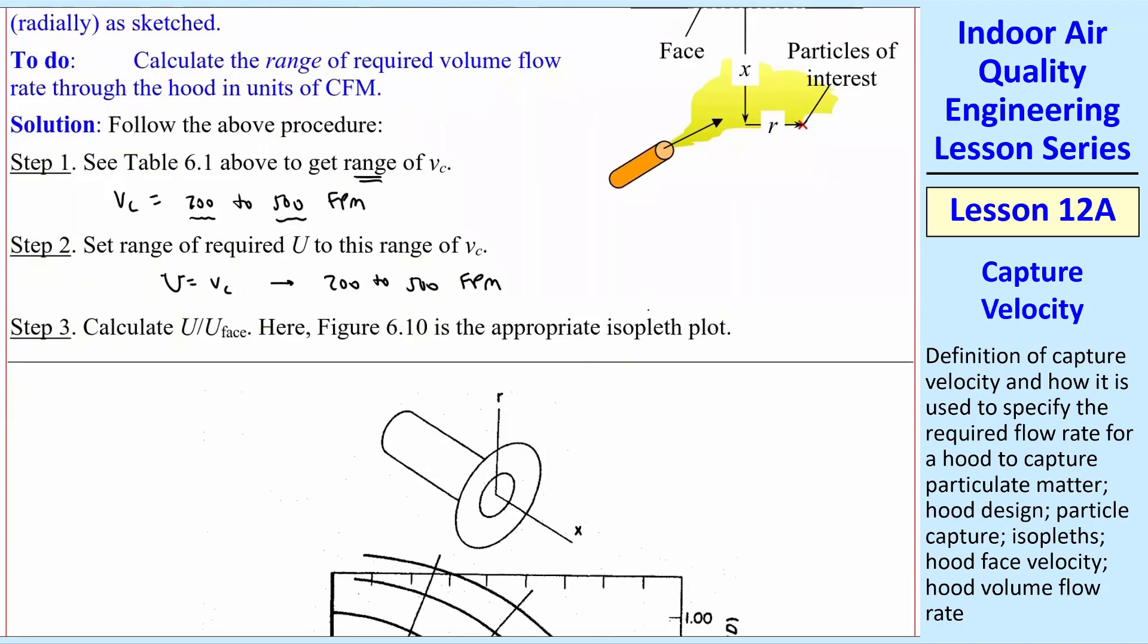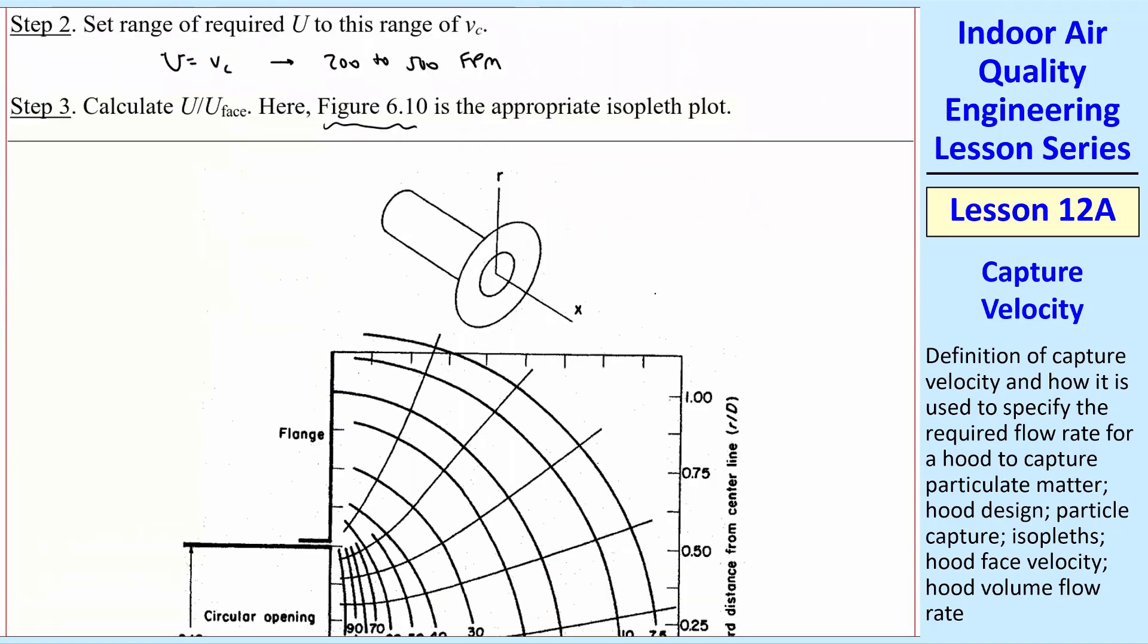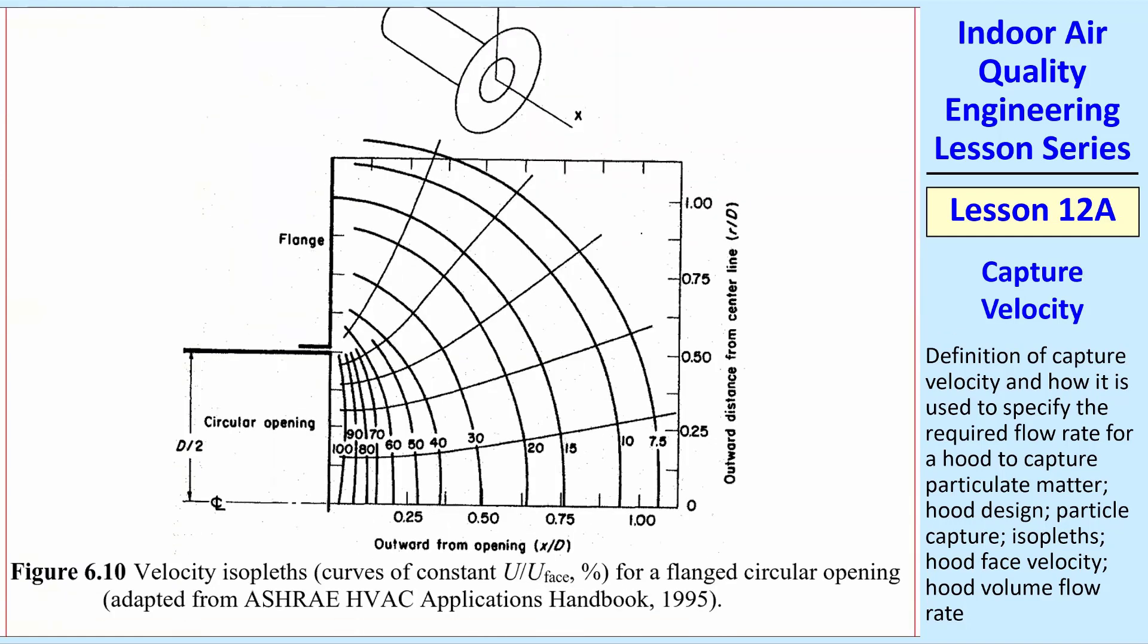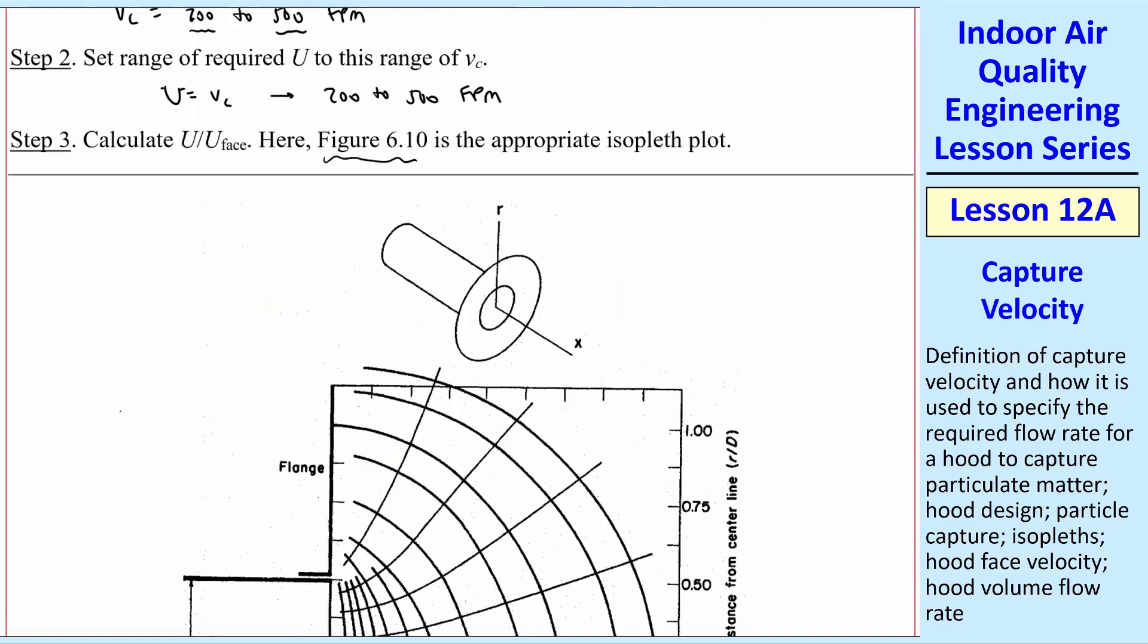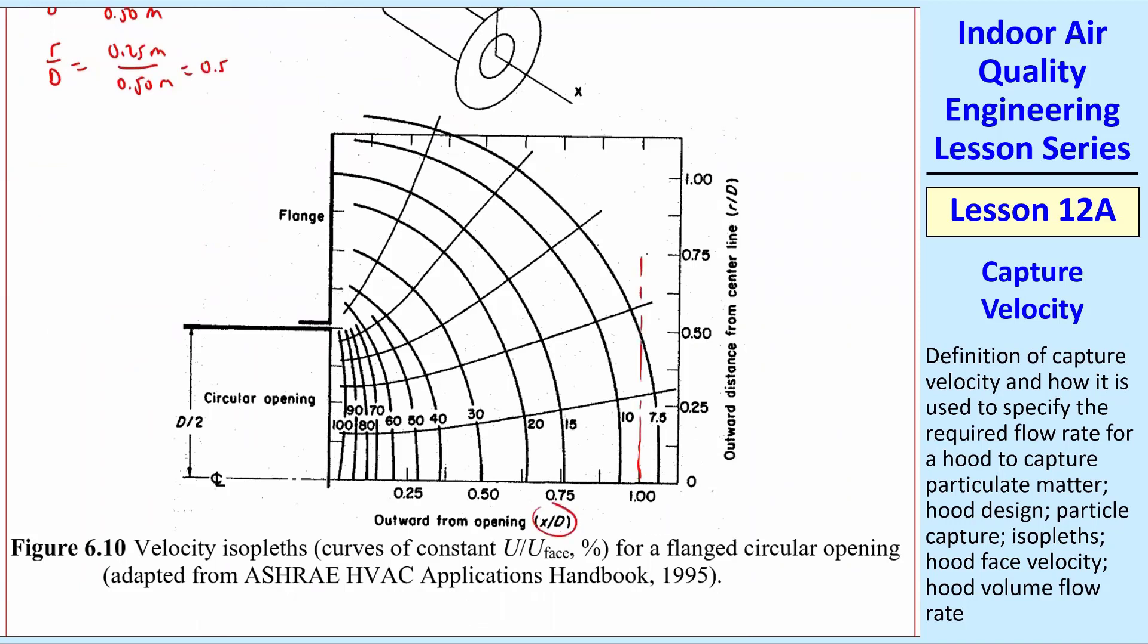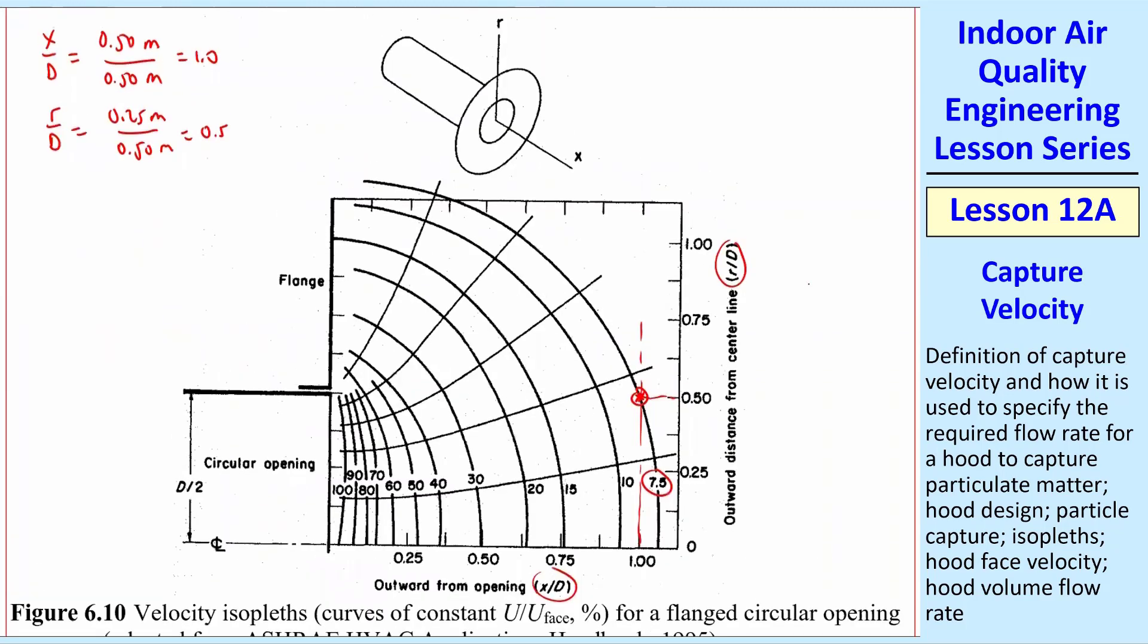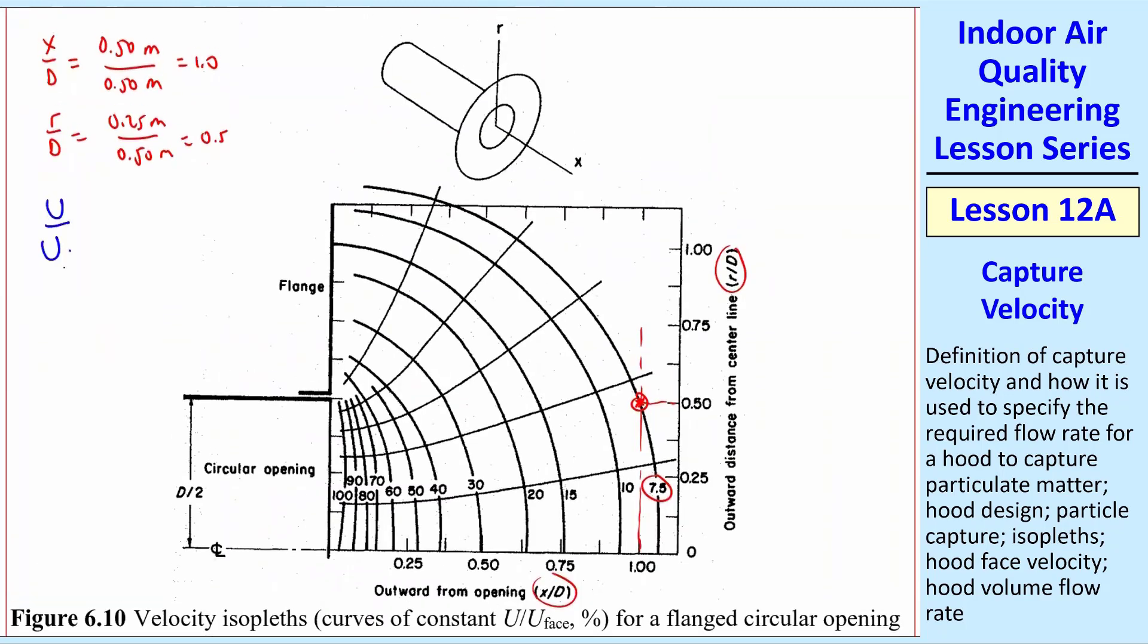Step three is to calculate U over Uface. So you pick the appropriate figure. Remember, we had figures like this 6.10. This is the one with the flange round inlet. So we use this. And since we're off the center line, we have to use the chart here instead of the equation for the center line. In this case, X over D was given as 1.0, and R over D was 0.5. X over D of 1.0, we go up, and R over D of 0.5, you go over. And that intersects almost exactly on this line, which is the 7.5% isopleth. Therefore, U over Uface, which is what we're plotting here, these isopleths, is 7.5% or 0.075.